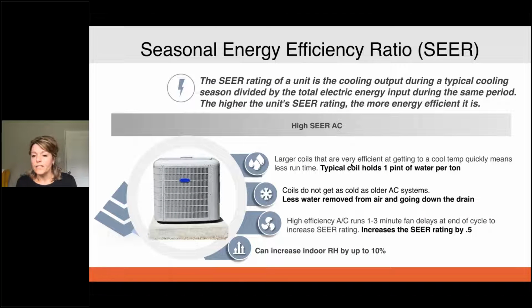So SEER, most of the higher performance building programs really encourage these higher SEER HVAC systems. And so what you need to understand about these systems is they're larger coils that are very efficient at getting to a cooler temp, which means less run time. So you lower that thermostat a couple degrees, it's going to come on and it's going to quickly be able to get to that lower temperature. And these coils on these higher HVAC systems typically hold about 1 pint of water per ton. So if you have a 5-ton system, you have 5 pints or pounds of water on those coils. The coils don't get as cold as the older AC system, which means less water being removed and going down the drain.